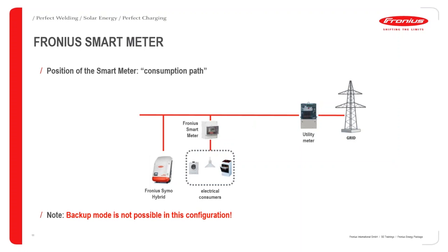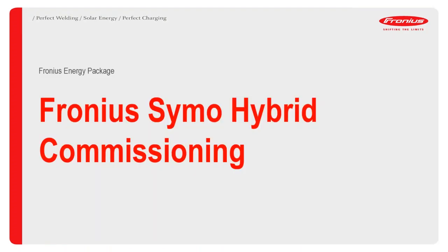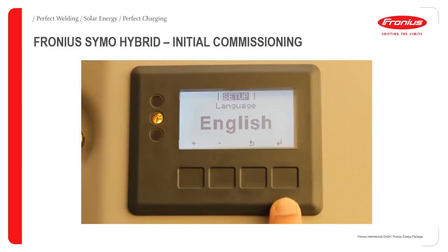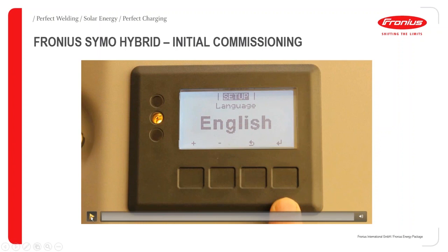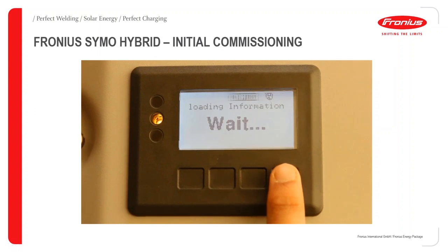If you're looking at the emergency power function, that's where the switch would sit. The meter needs to go between the contactor and the utility meter, so that when the grid comes back, the meter can detect it. The other point, which is shown on the Datamanager or the hybrid manager as being the consumption path, would look like this. So you can see essentially the inverter is on the grid side of the Fronius smart meter, not on the load side. That rarely happens here in Australia unless you've got gross metering, possibly in New South Wales, but they're coming off that anyway. That particular constellation could get used in Europe.